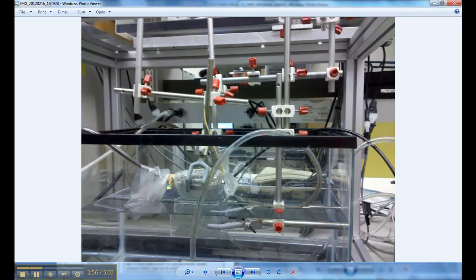This here is the focus transducer. It's in a bag filled with degassed water. We have to have some sort of acoustic coupling between the transducer and the vessel. However, the vessel has to be in saline. That's why this isn't all done underwater. This box here is full of saline and contains the vessel, and then the focus transducer here behind it, which you can't see, would be the unfocused transducer acting as a microphone, and that's just in the tank of water on the outside of the box.